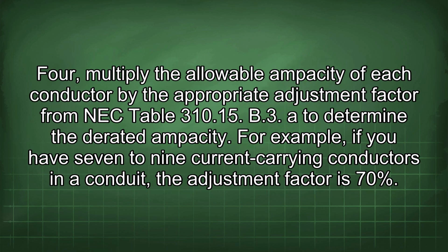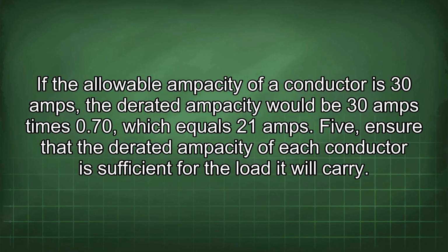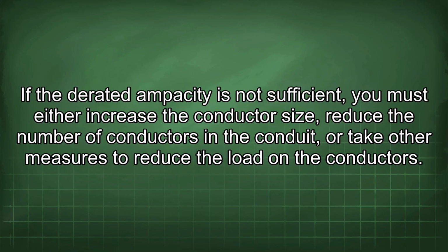4. Multiply the allowable ampacity of each conductor by the appropriate adjustment factor from NEC Table 310.15(B)(3)(a) to determine the derated ampacity. For example, if you have 7 to 9 current-carrying conductors in a conduit, the adjustment factor is 70%. If the allowable ampacity of a conductor is 30 amps, the derated ampacity would be 30 amps times 0.70, which equals 21 amps. 5. Ensure that the derated ampacity of each conductor is sufficient for the load it will carry. If the derated ampacity is not sufficient, you must either increase the conductor size, reduce the number of conductors in the conduit, or take other measures to reduce the load on the conductors.